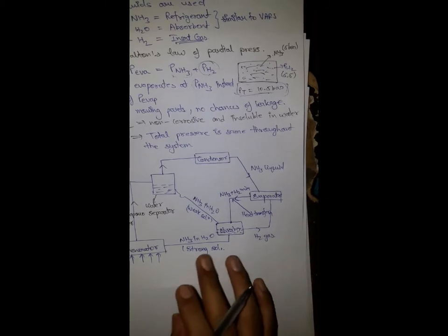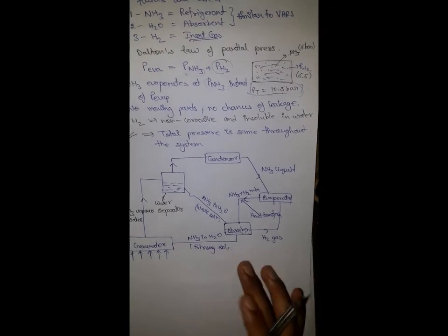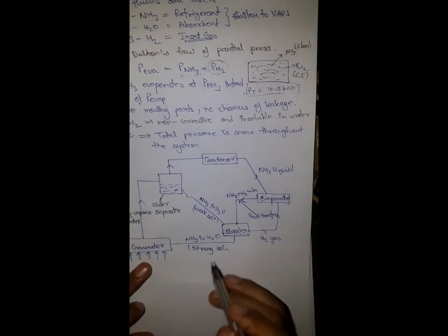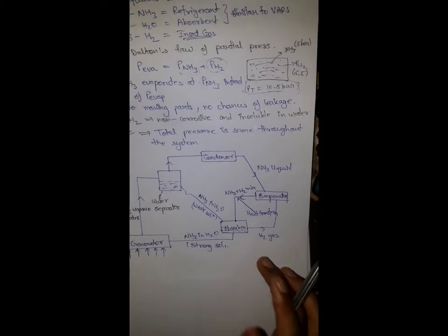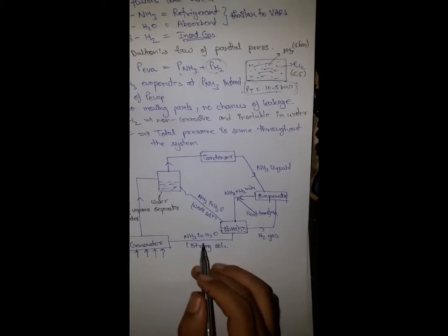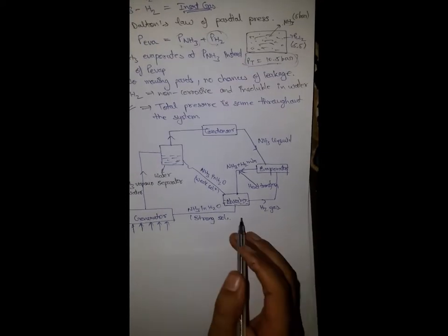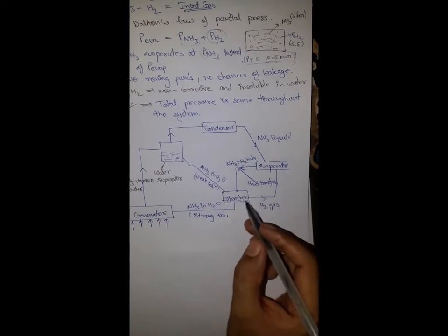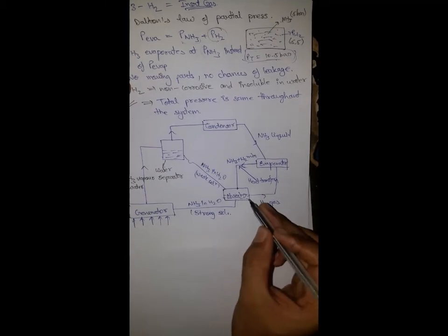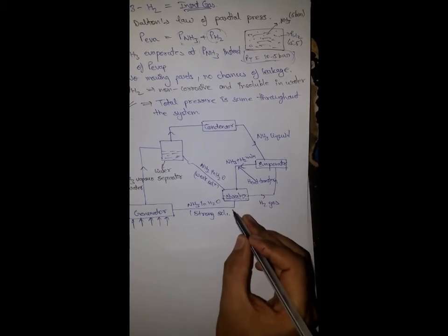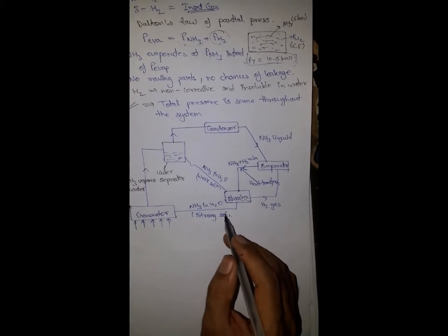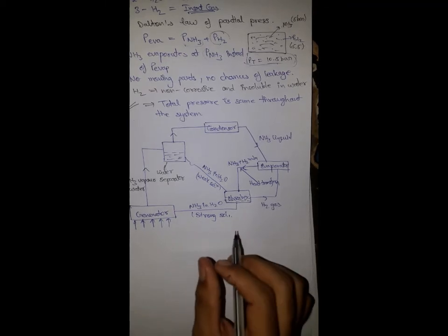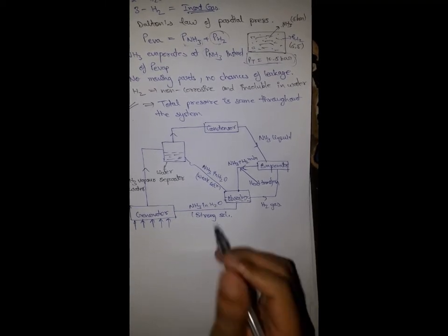So now let me brief it in a short time. What is actually happening? This Electrolux refrigeration is similar to the vapor absorption refrigeration system. The key difference is the use of hydrogen as an inert gas over here. Similar to the vapor absorption refrigeration system, we are having a generator and absorber over here. In the absorber, the strong solution of ammonia refrigerant is present, which is circulated to the generator, but we are not using a pump over here. It is circulated due to the pressure difference. We would talk about this point in the next video.